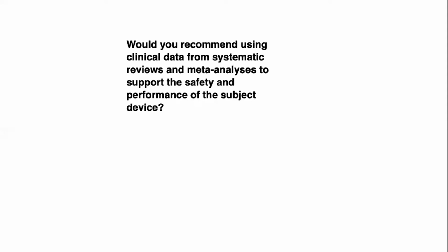Systematic reviews and meta-analyses are commonly pooled data, or they're not the primary source of data. And certainly if it represents pooled data, that means that data within those meta-analyses or reviews is a mix. To support the safety and performance of your own device, you must use data directly on that device and not mixed with anything else.